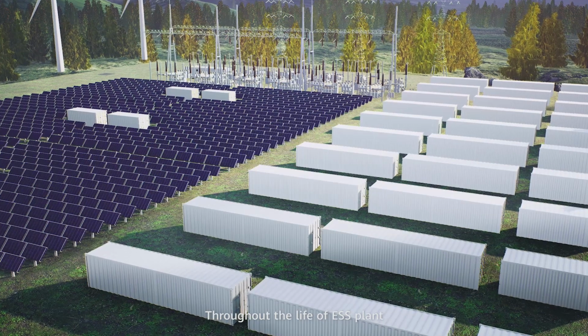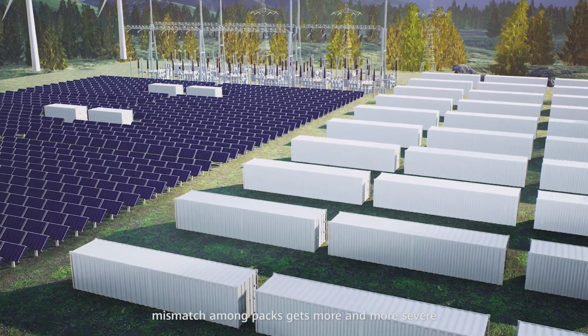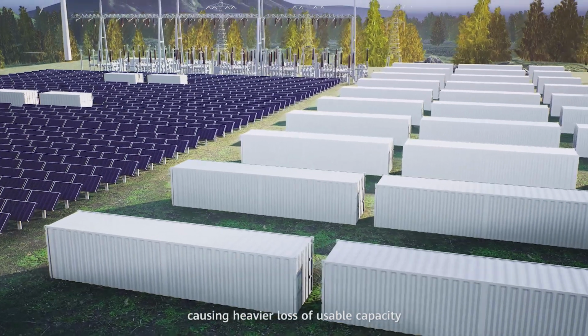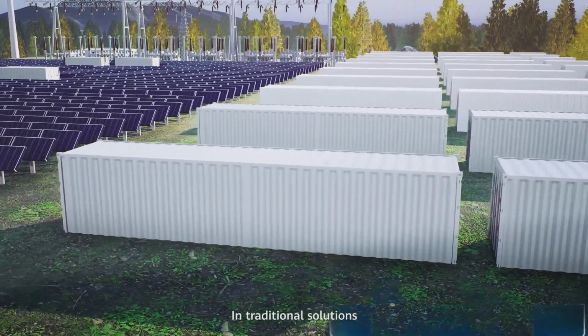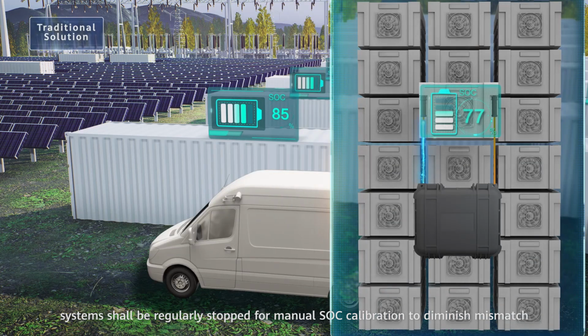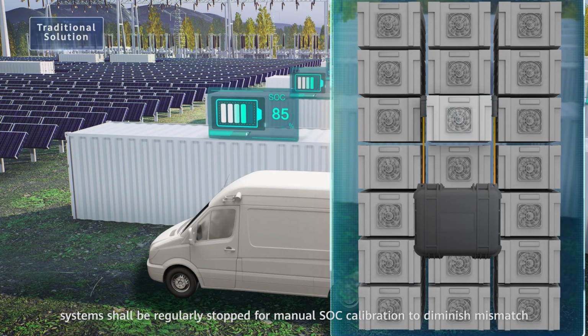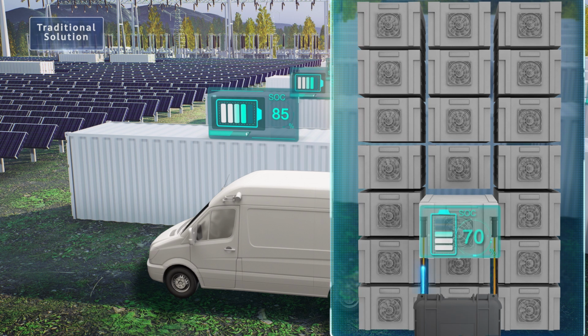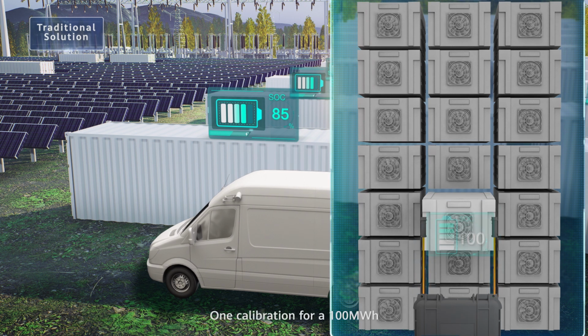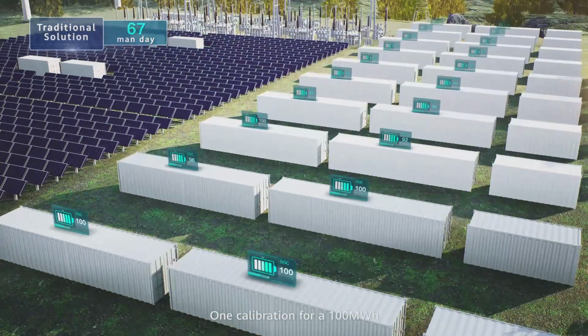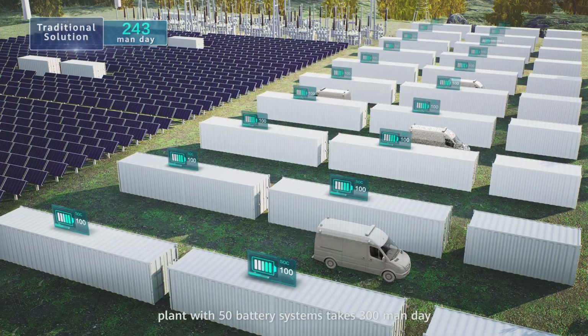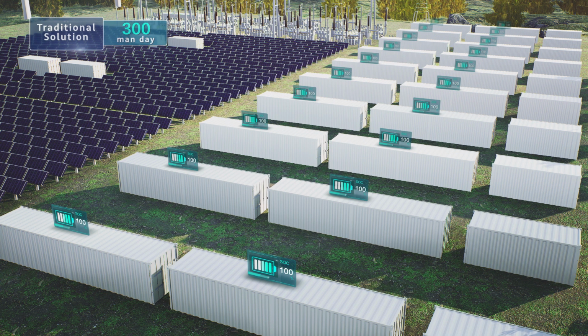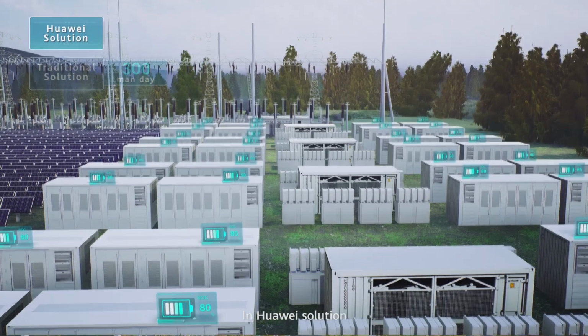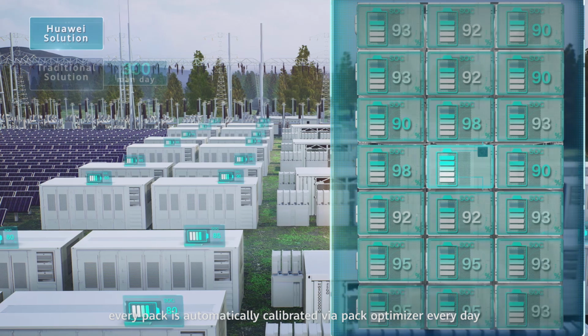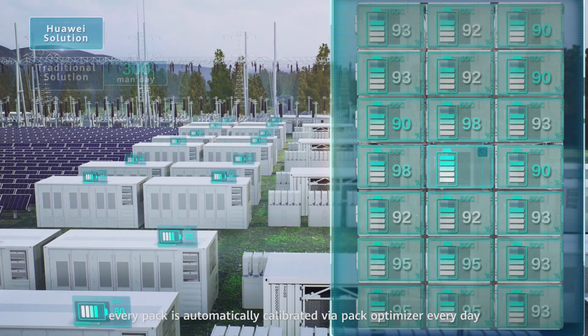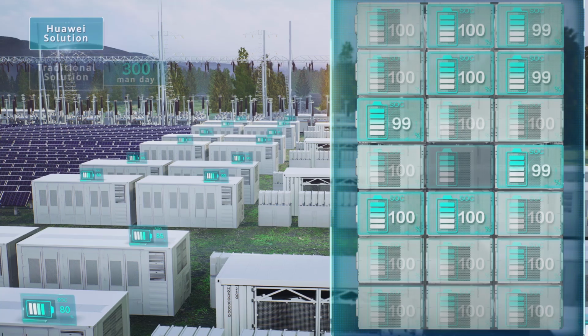Throughout the life of ESS plant, mismatch among packs gets more and more severe, causing heavier loss of usable capacity. In traditional solutions, systems shall be regularly stopped for manual SOC calibration to diminish mismatch. One calibration for a 100 megawatt-hour plant with 50 battery systems takes 300 man-days. In Huawei solution, every pack is automatically calibrated via pack optimizer every day. No need of system shutdown.